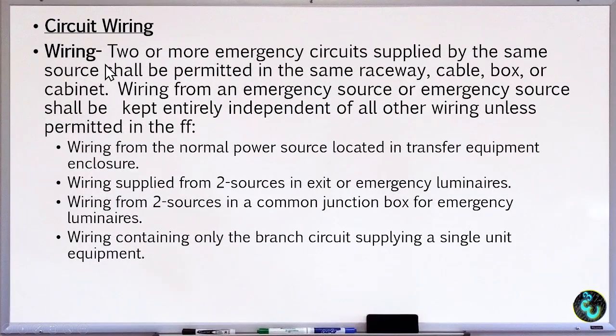So the wiring for our emergency system. Two or more emergency circuits supplied by the same source shall be permitted in the same raceway, cable, box, or cabinet. Wiring from an emergency source shall be kept entirely independent of all other wiring unless permitted in the following.